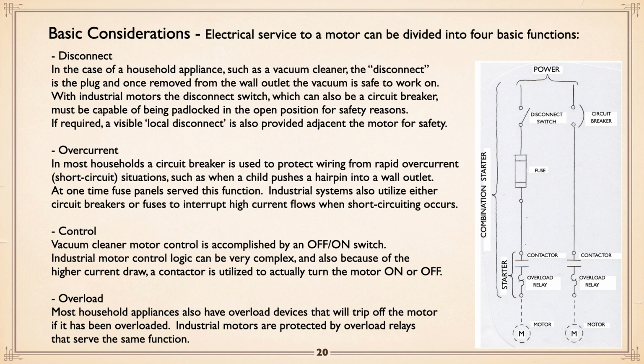Here is sort of your big introduction to how this stuff works. There are 4 elements that make up a service to a motor. The first of these is a disconnect. Now, you get exactly the same thing with household stuff. Let's pretend you have a vacuum cleaner. Well, a disconnect is the plug. So if you're going to clean the vacuum cleaner, you should go and unplug it first, right? Now, with industrial motors, it's the disconnect switch. Circuit breakers serve the same function if they can be locked out, which we'll get into later. So disconnect switch or service breaker, that provides your disconnect needs. And if the motor is remote, then you're required to have another disconnect switch between all this equipment and the motor itself, within sight of the motor, and you can padlock that or whatever.